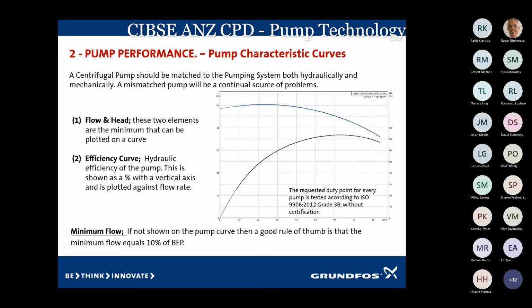The efficiency curve, the black moon-shaped arc there, is the hydraulic efficiency curve. That's indicating where the pump likes to run. What we call the best efficiency point, the BEP, is always up at the peak. The peak of this one is around about 60 litres a second. If you have a look at 60 litres a second, where it meets the BEP, the best efficiency line, we take our eye to the right, and that gives us our efficiency. So at 60 litres a second, the best efficiency is about 72%.